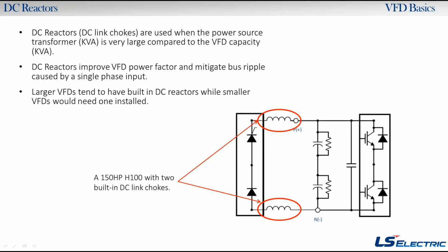DC reactors are commonly included on VFDs above a certain capacity. DC link chokes are used when you have a very large power source compared to a very small drive. For example, your transformer could be oversized and your drive is really small. That could cause an issue just because it's so different. The power is so stiff, is something that they say. Your transformer is a stiff transformer. That could cause issues, but a DC reactor, or DC link choke as we also call it, will help out. This is also going to improve power factor.